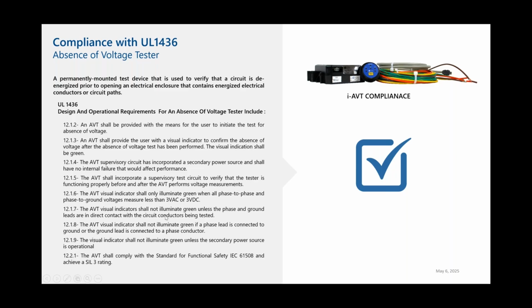The AVT visual indicator shall not illuminate green unless the phase and ground leads are in direct contact with the circuit conductors being tested. And the AVT visual indicator shall not illuminate green if a phase lead is connected to ground or the ground lead is connected to a phase conductor. So that's in the event of a ground fault condition that's existing on the system, even in the de-energized state. The visual indicator shall not illuminate green unless the secondary power source is operational. And also we have to comply with the standard for functional safety in IEC 61508 and also achieve an SIL3 rating, which is a safety rating for the device, to ensure that there are no false positives, false negatives, and that the unit is able to withstand a large number of tests before it actually fails.